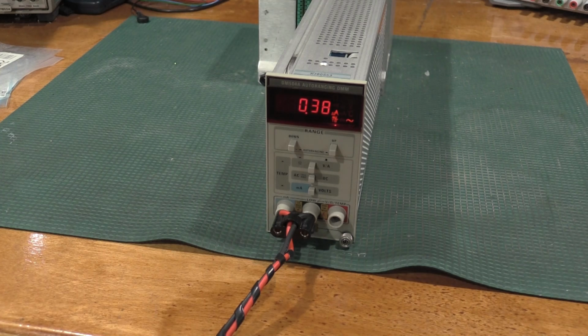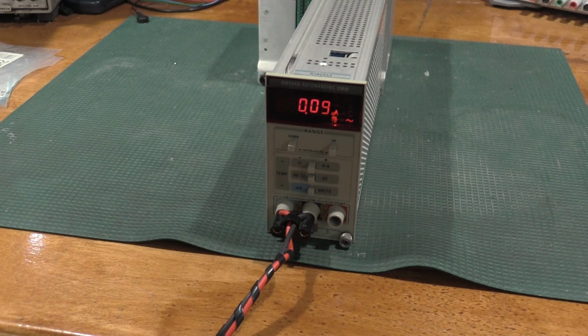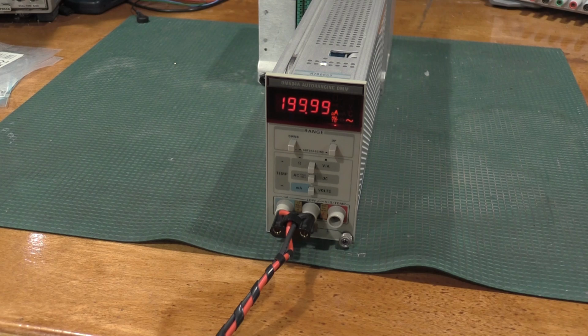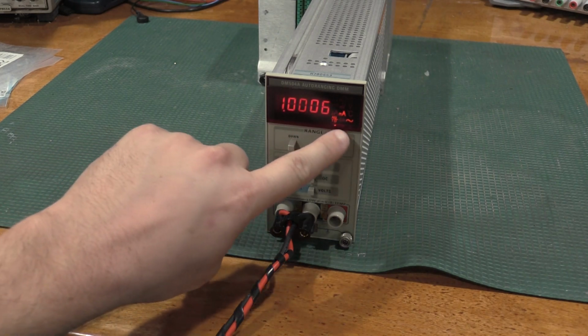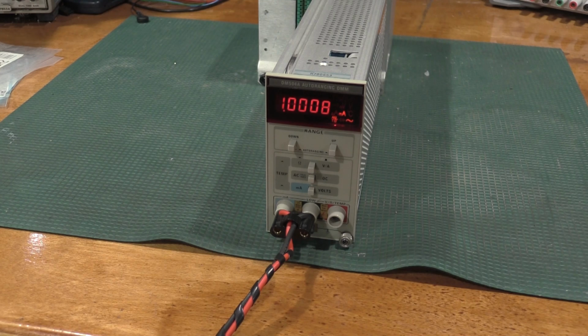Okay, time to do the exotic one that was causing me some problems. To get this measurement, we have the Valhalla Scientific 2500 on the 1 milliamp range. We have the Fluke 5200A outputting 10 volts at 100 hertz into the Valhalla Scientific. And the Valhalla Scientific is going to generate, theoretically, 1 milliamp of AC current. This one gets a little wild. So we're going to take that to operate, and we have 1 milliamp of AC. So the meter is doing incredibly well.